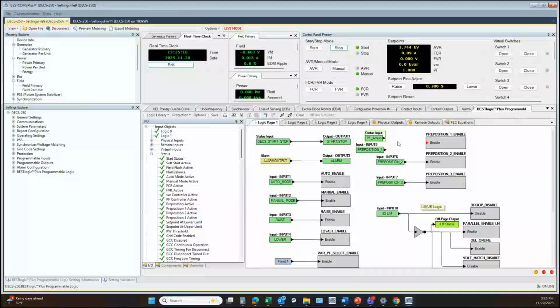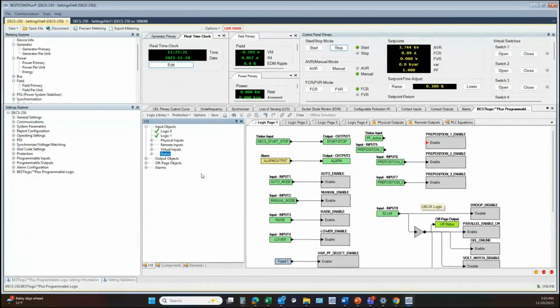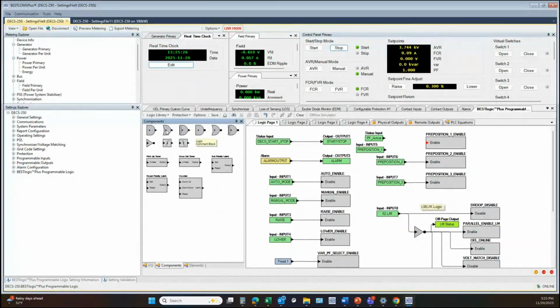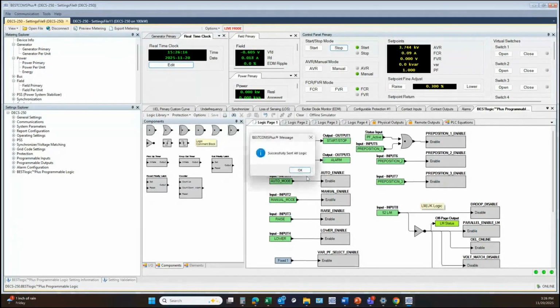But if I want to keep input 5 or power factor active, what controls my preposition, then I would need a component, an actual logic gate known as an OR gate. So an OR gate, if any of its inputs become true, then its output becomes true. So if I connect that, then once I'm in power factor control mode, this status input will become active, and then that will trigger the preposition 1. So my pre-positioned setting for power factor control mode will then cause my power factor set point to change to whatever the pre-position value is. So I can save that and then upload that logic to the unit as well.